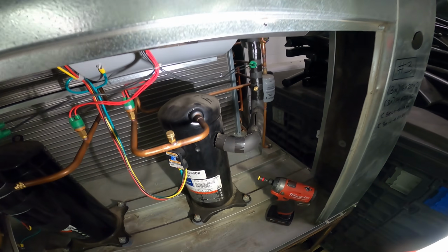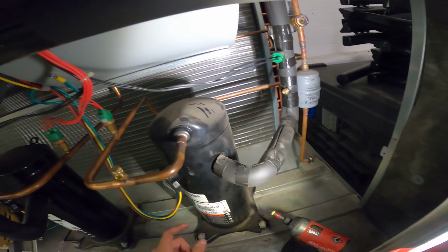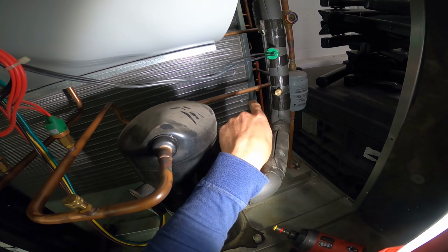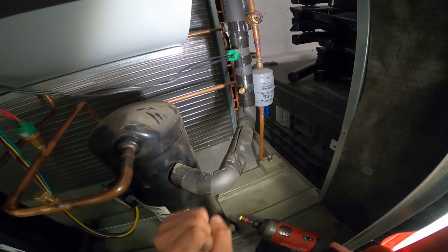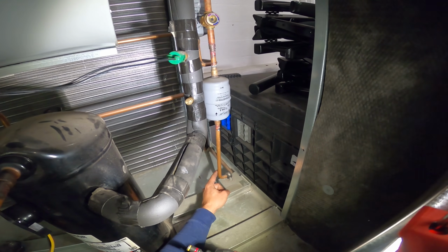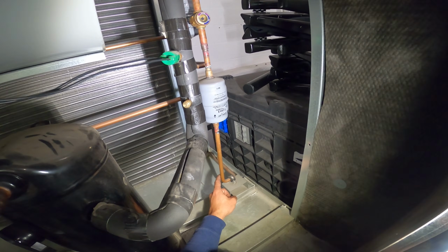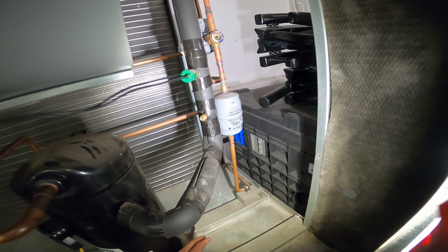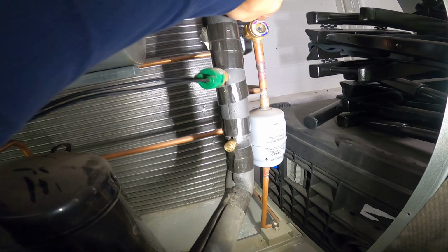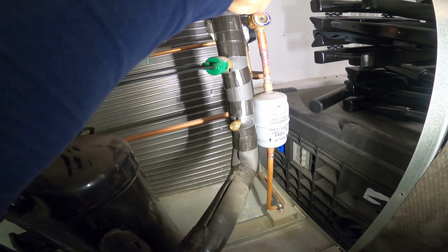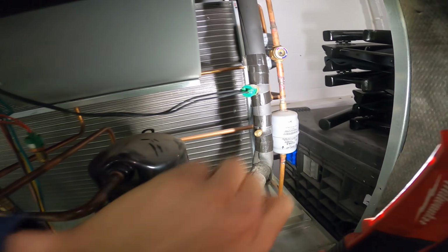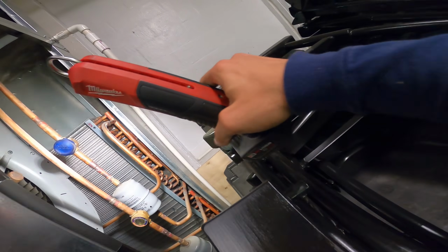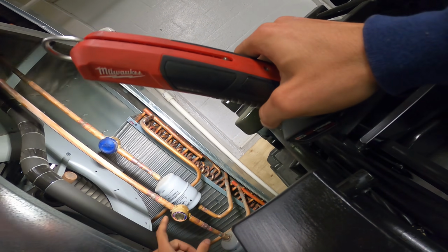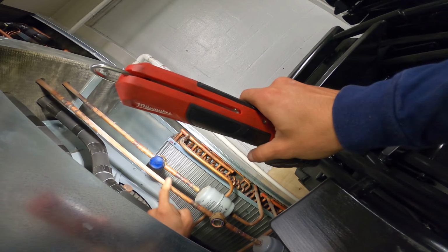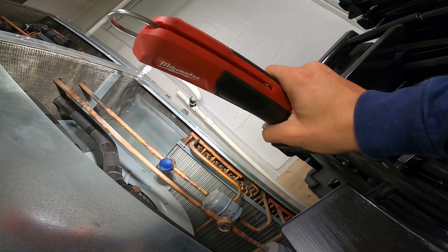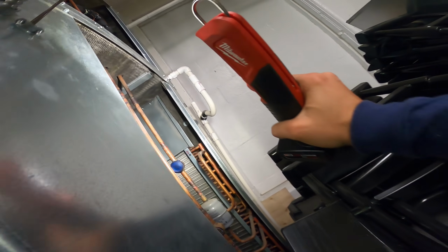Okay, if we follow along over here, the discharge line goes into the condenser, and coming out of the condenser, it's going to be your liquid line. Your liquid line is going to have multiple components in it. You're going to find things like this right here. This is your filter dryer. Next, on the same line, right here, this is your sight glass. You can physically see if the refrigerant is being fully condensed. In this circuit, since we have two compressors, we have two filter dryers and two sight glasses. And that's your liquid line, and that makes its way up to your expansion valve, which then ends up leading into your evaporator. So let's make our way up there.